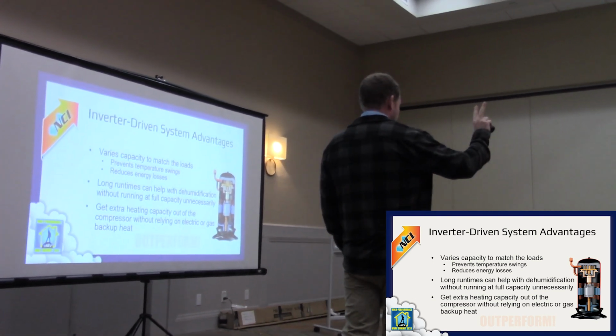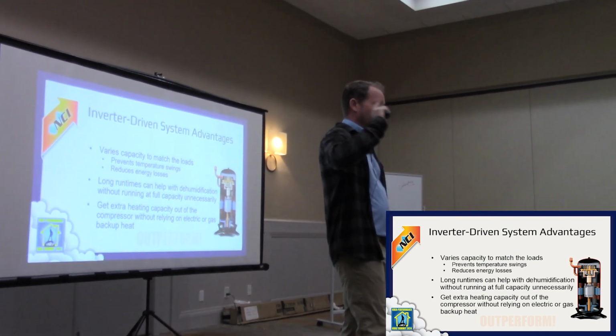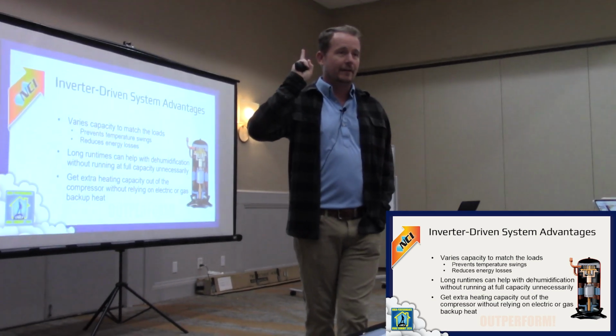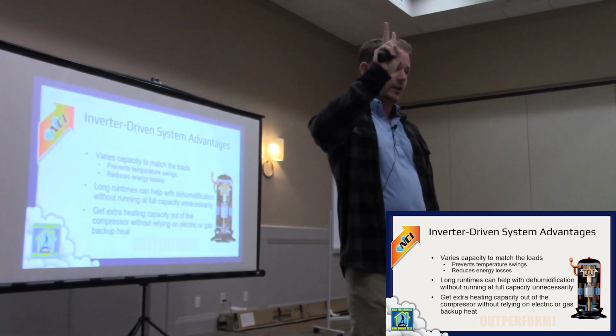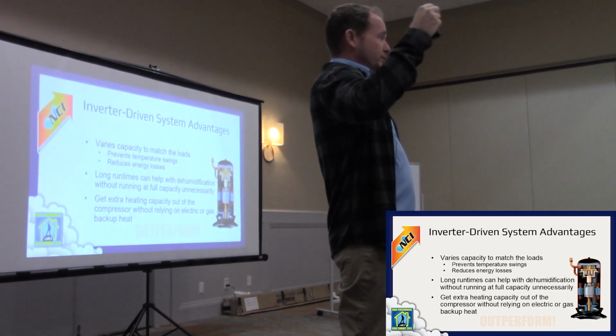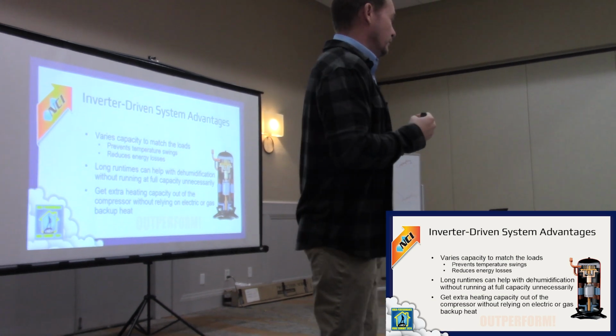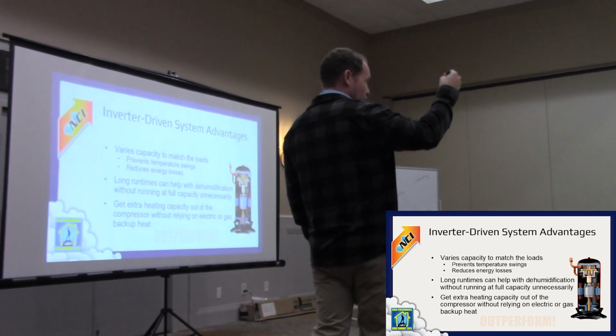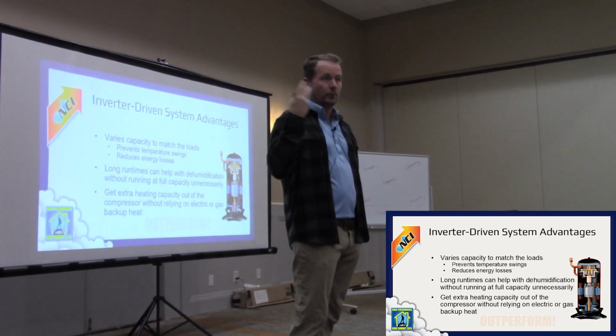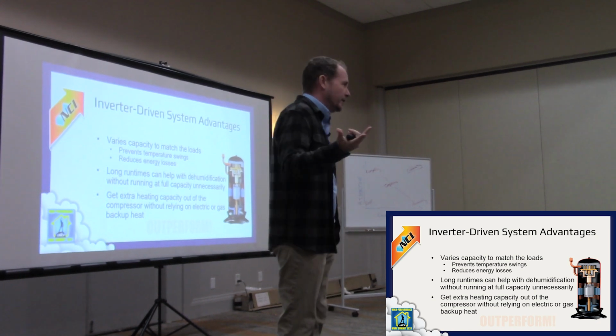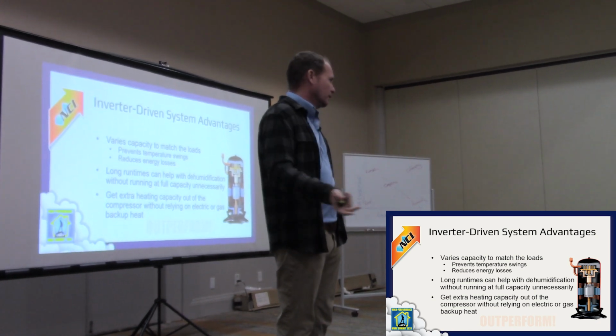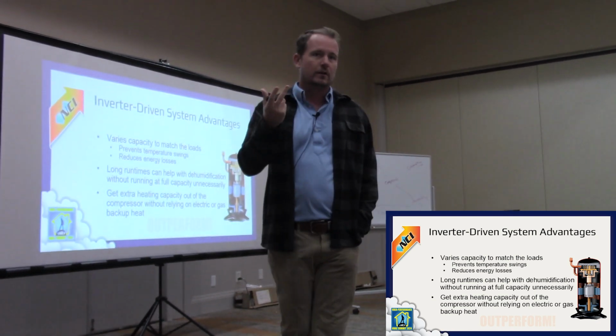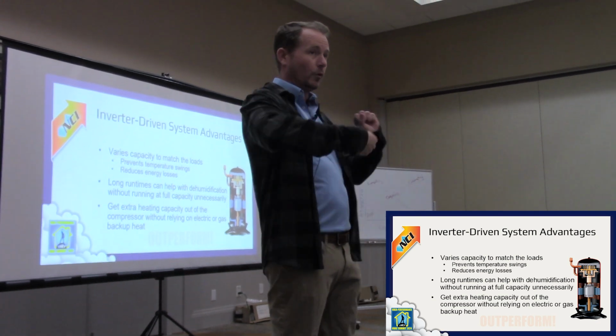There's two things you need to do in order to get moisture out of a space. You need to have long run times, and you need to have cold evaporator temperatures, right? Any evaporator temperature below dew point is going to pull some moisture. But the further you are below dew point on your evaporator coil, the more moisture you're going to pull. We all know this, right? You run your blower slower, run air over the evaporator coil slower, you're going to pull more moisture out of the air. You're going to wring more out, right?